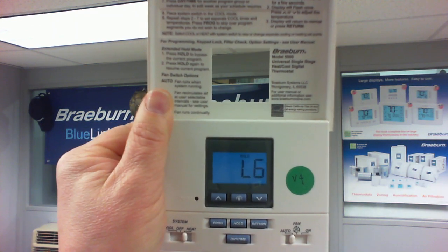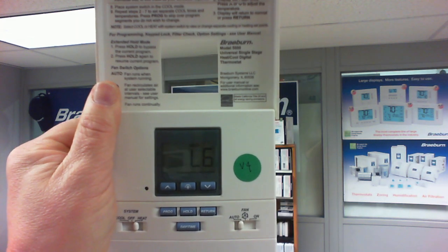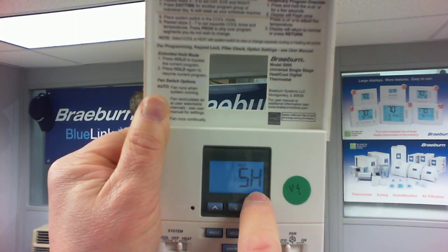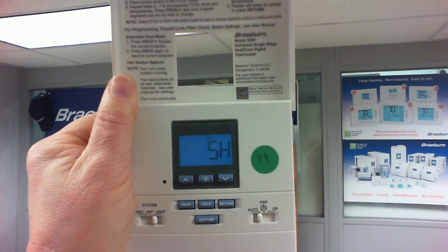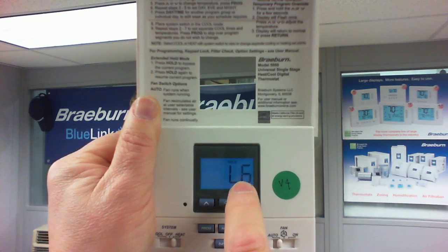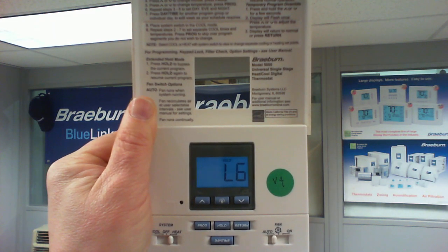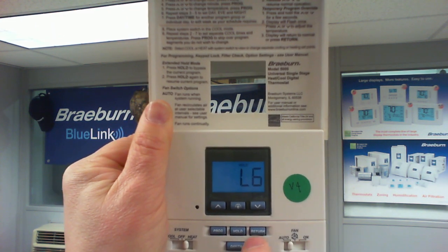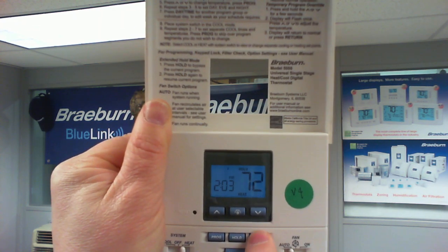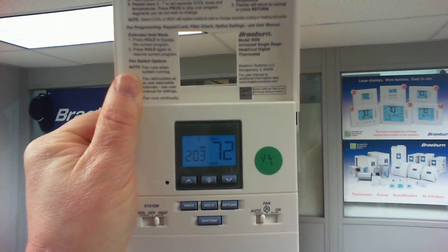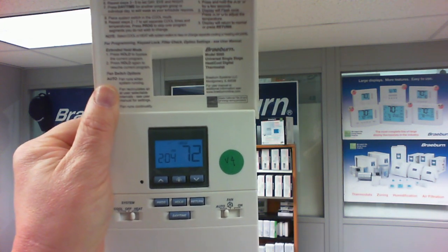You want this to be on LG. It looks like a 6, but that's supposed to be a G. LG is a long hold, meaning indefinite. If you leave it on SH, every time you use the hold feature, it will expire after 24 hours. So we want to make sure that we're using LG. Once you have it set on LG, if you just leave it alone, it will self-exit after about 30 seconds, or you can continue pressing the return button to cycle through the rest of the options until you get back to your operating screen.